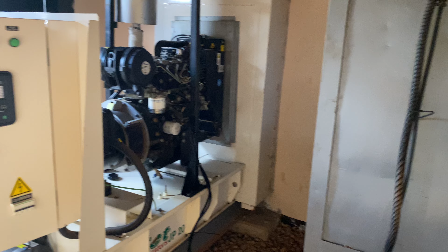Let me start with the controller panel. This is our controller panel for this 20 kVA diesel generator, AC generator, 3-phase generator. We always use it to start and stop the generator manually by pressing here and here, also to put it in auto mode in case it is connected to the ATS, that is the automatic transfer switch, and it also shows us indicators in case of any problem.